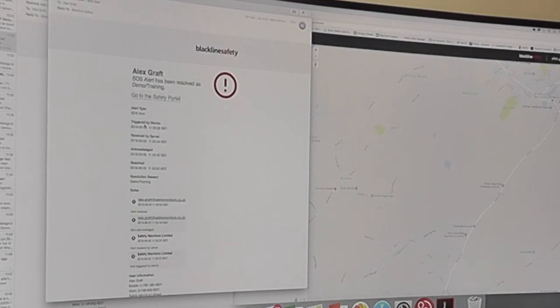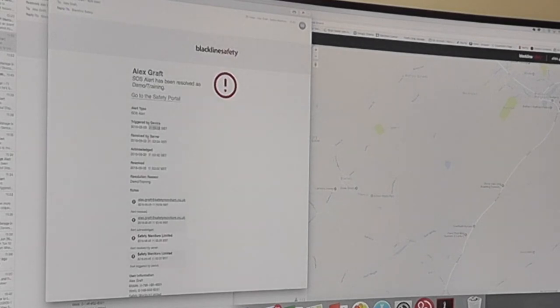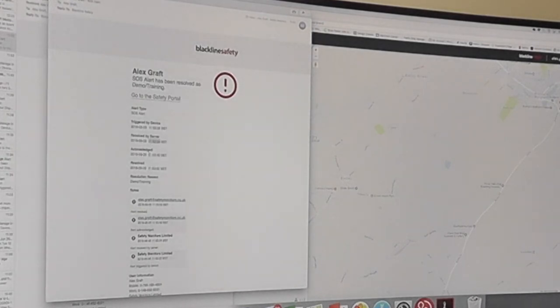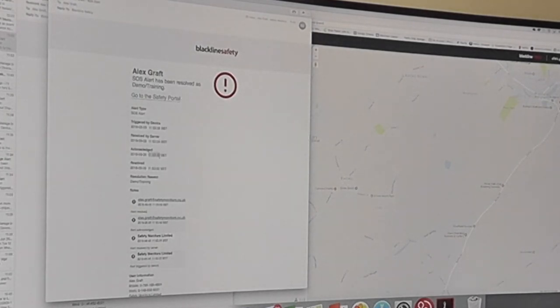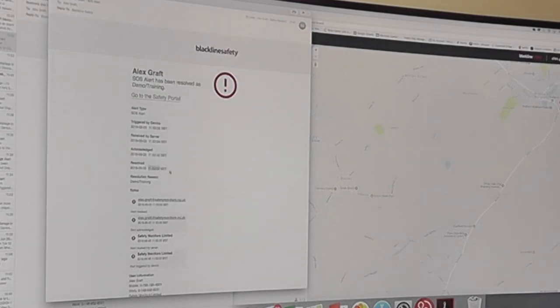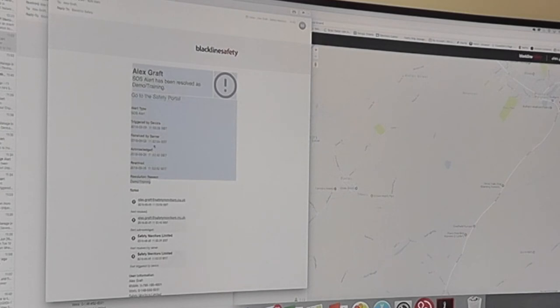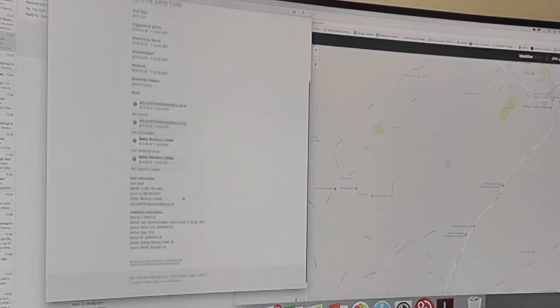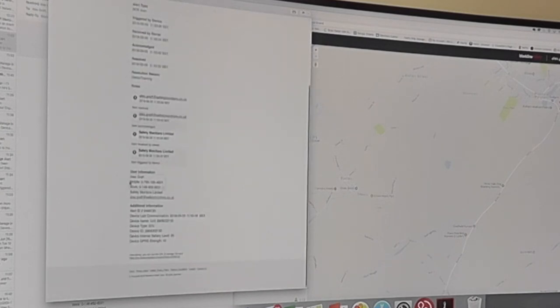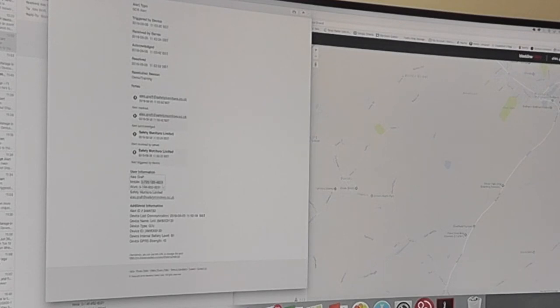And then we can see when the unit was resolved. We can see that it was originally triggered by the device at 22 seconds past 11:53, received by the server two seconds later. It was acknowledged here in the office about 15 seconds after that and was completely resolved 10 seconds later. And it also gives you an option for the resolution and reason, so we get a full history of exactly what's gone on. Also any information about the user in terms of mobile numbers, contact telephone numbers, email addresses, and anywhere else other alerts were sent including telephone numbers.